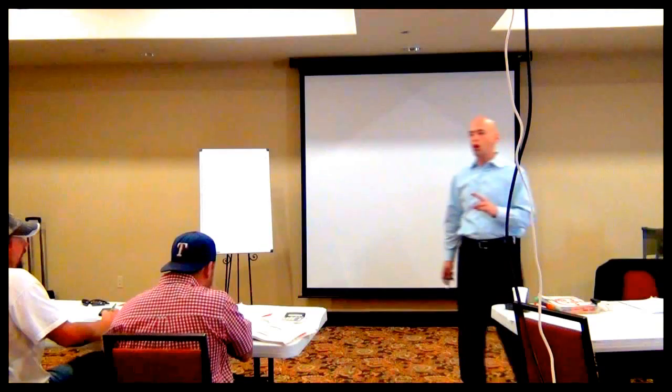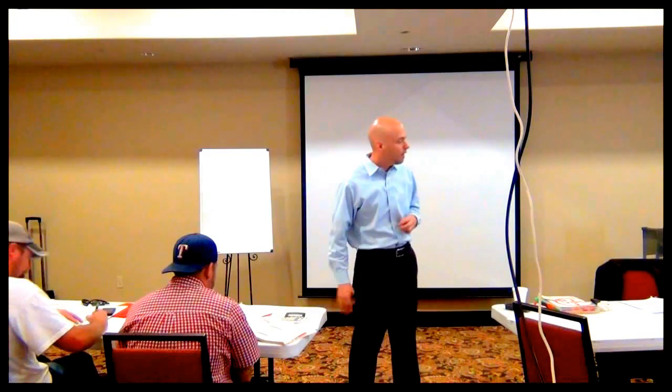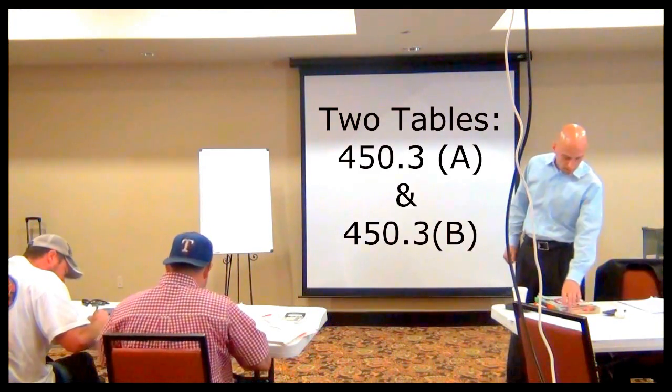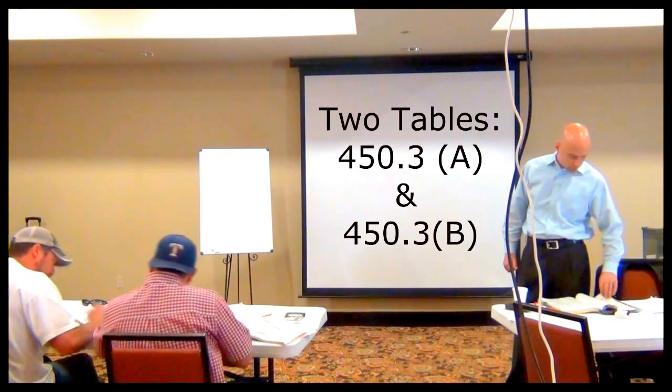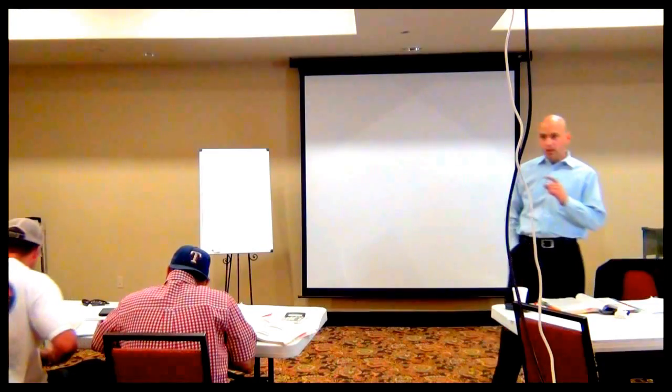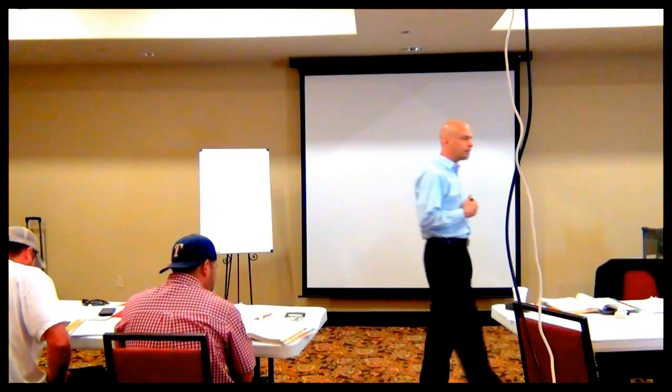The math is a constant. There are two tables we use to size overcurrent protection for a transformer — that's under 450.3 A and B. When dealing with a transformer, the very first table on top, Table A, is for transformers rated over 600 volts. The one below that, the smaller one, is for transformers rated 600 volts or less.